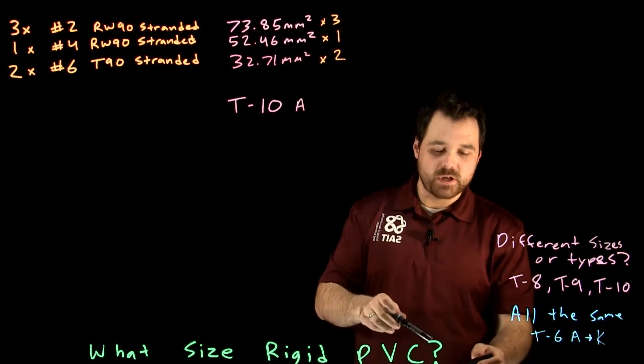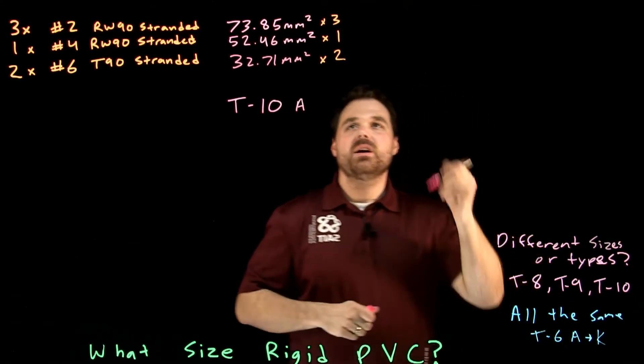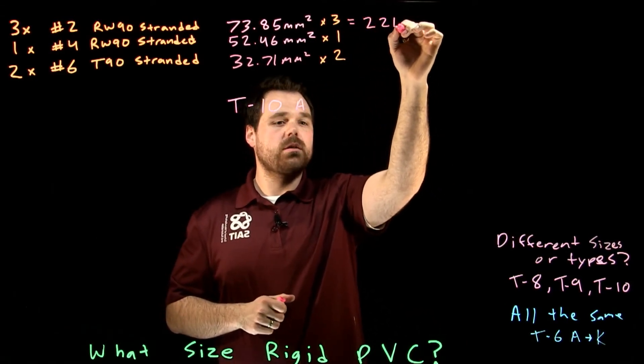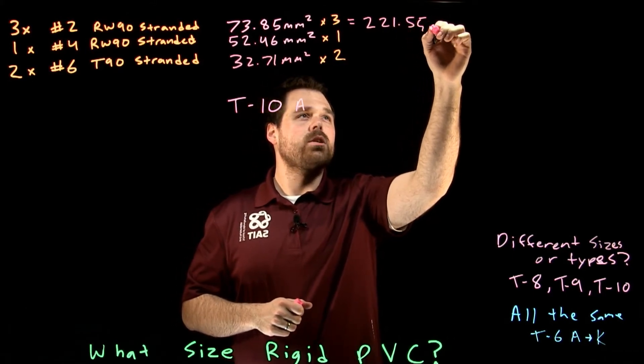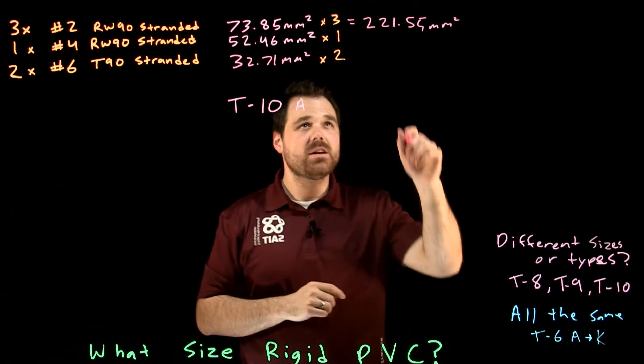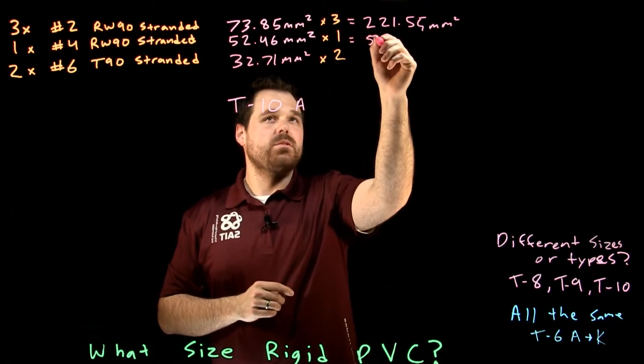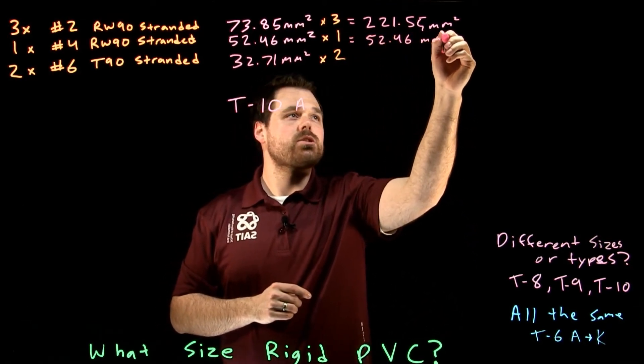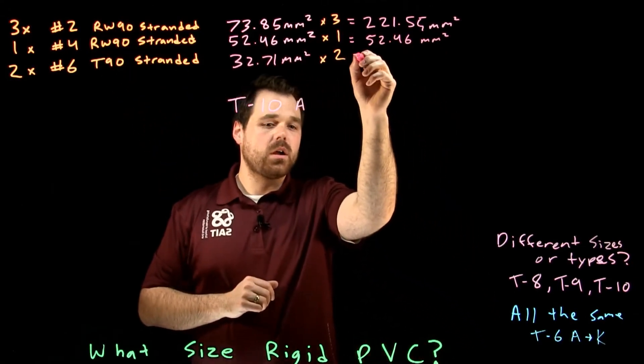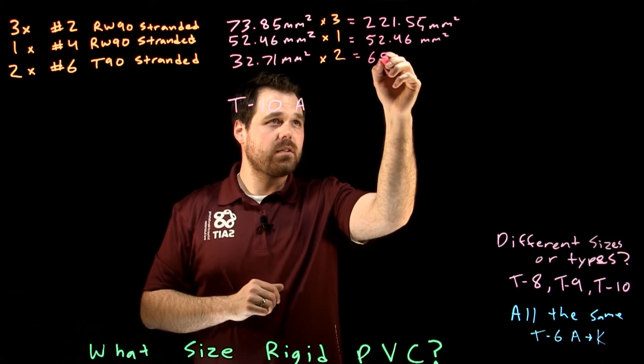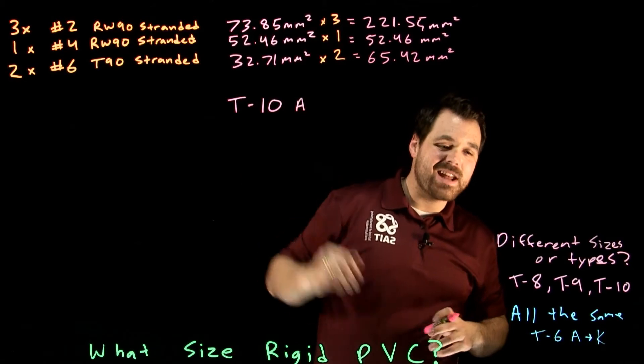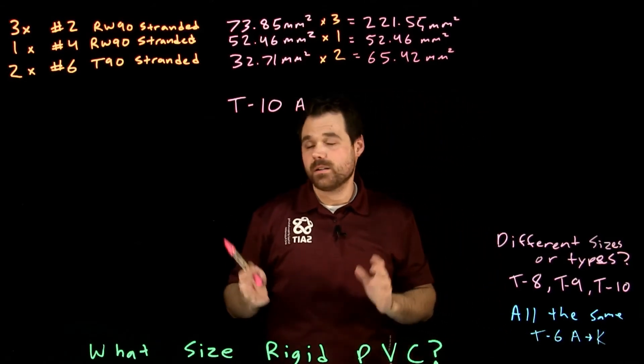So we do the math really quick. That gives us two hundred and twenty one point five five millimeters squared for my three number two RW90s. We get fifty two point four six millimeters squared for my one number four. And we get sixty five point four two millimeters squared for my two T90 number sixes.